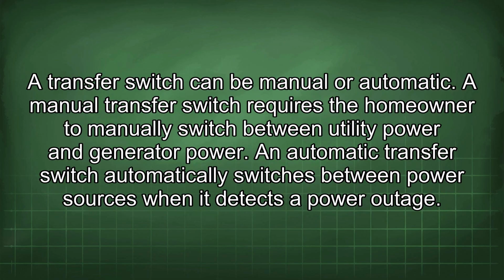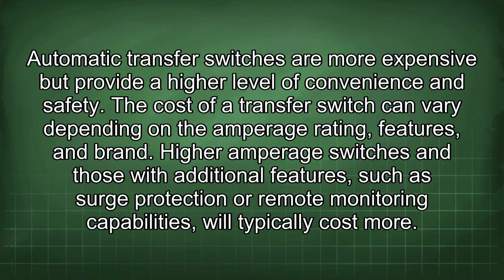A transfer switch can be manual or automatic. A manual transfer switch requires the homeowner to manually switch between utility power and generator power. An automatic transfer switch automatically switches between power sources when it detects a power outage. Automatic transfer switches are more expensive but provide a high level of convenience and safety. The cost of a transfer switch can vary depending on the amperage rating, features, and brand. Higher amperage switches and those with additional features such as surge protection or remote monitoring capabilities will typically cost more.